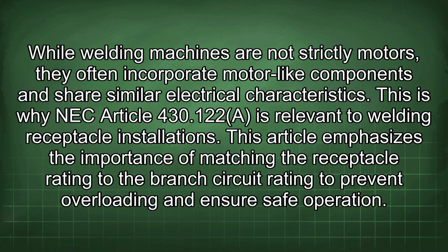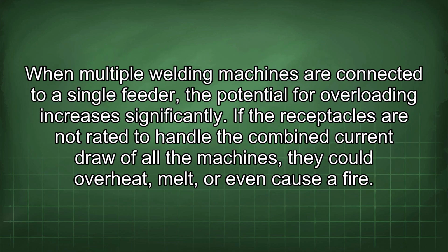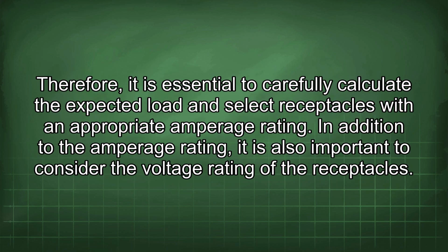When multiple welding machines are connected to a single feeder, the potential for overloading increases significantly. If the receptacles are not rated to handle the combined current draw of all the machines, they could overheat, melt, or even cause a fire. Therefore, it is essential to carefully calculate the expected load and select receptacles with an appropriate amperage rating.